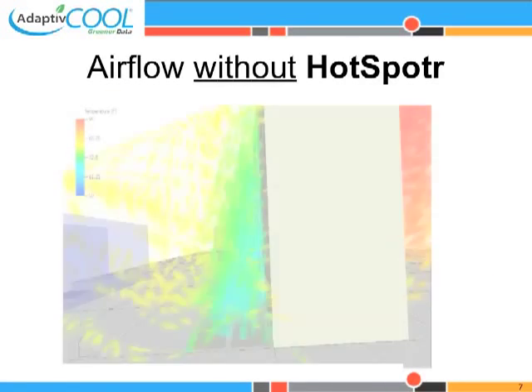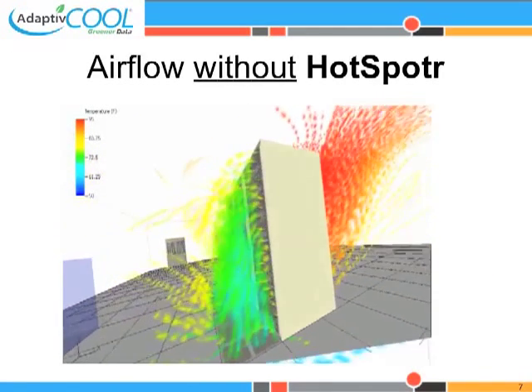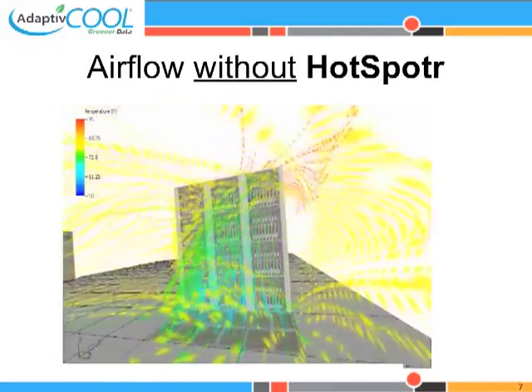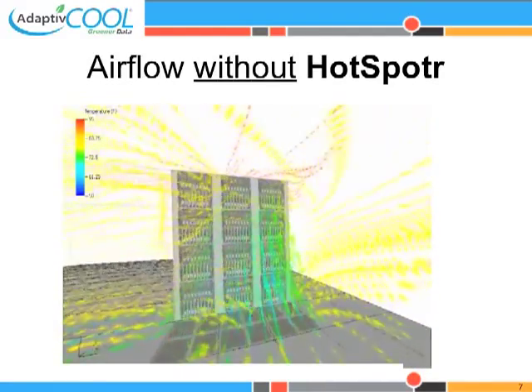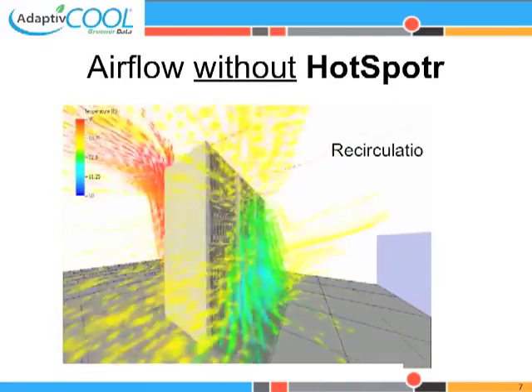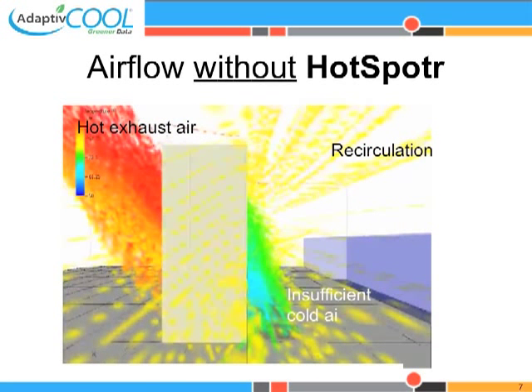In this animation showing airflow and temperature at a server rack, you can see recirculation of hot air from other areas. This is because the cold air discharged from the floor is not high enough. This also results in high exhaust air temperature.